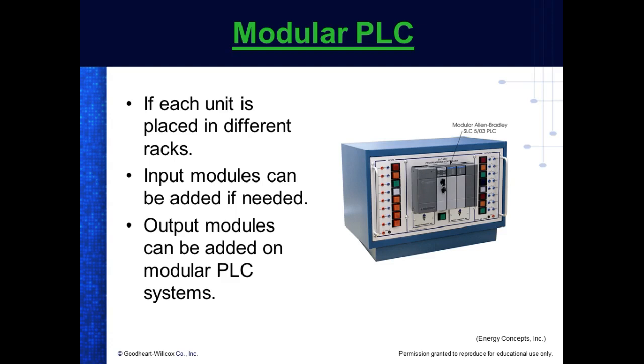On this, if I lose one of my outputs, I'm screwed. If this, I lose one of my outputs, all I might have to do instead of buying the whole PLC, I can do what? Just swap the module out. Just get a new module. I could carry spare modules. If all my PLCs are the same, right, you understand, then I could have a spare module in there. If I burn one of them out, I could be back up and running in almost no time at all. So these guys are easy to troubleshoot, right? You understand? They're very flexible, they're very expandable, and they're very expensive.